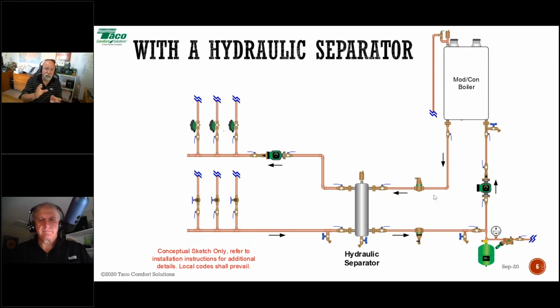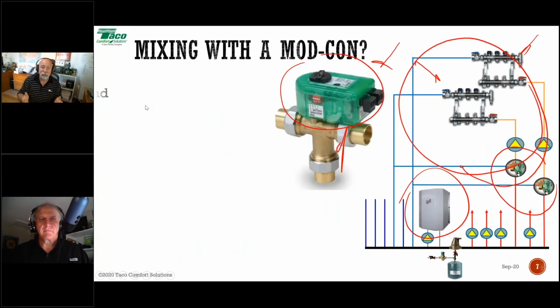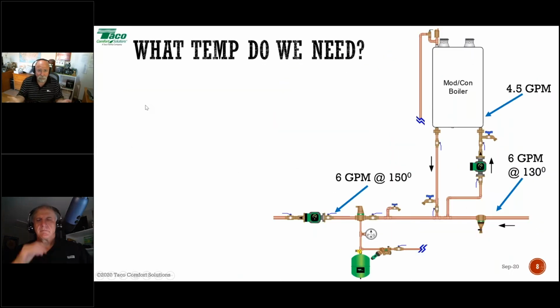So, for instance, if you wanted 1.5 inches on the secondary going out to the system, then they're just going to make the other side, and you could bush it down. It absolutely could be less than. A lot of times when we're talking primary secondary, the actual primary portion, those twin T's of the boiler, are one, sometimes maybe even two pipe sizes smaller than the secondary, because we might have a bigger delta T on the boiler, which is what we're going to talk about later, than we do on the system. So the system piping might be bigger than the boiler piping, and a lot of times is. So there's nothing wrong with that based on some of the things we're going to talk about. John's already showed you now. It's going to show you right now, and I'm going to get into later as well.